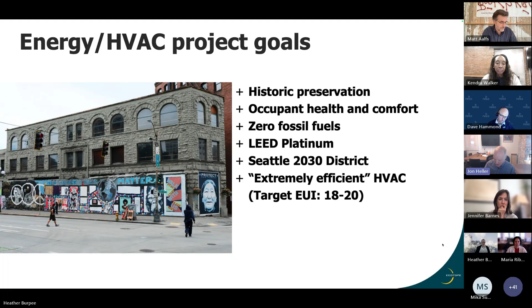Next slide. So the first focus on this shell of a building was bringing the heating load down as much as possible while maintaining the historic character of the masonry walls inside and out. In order to have a well-insulated envelope while still maintaining a lot of the exposed masonry, we focused on getting the best windows available—triple pane wood windows delivering a U value of less than 0.2. That allowed us to just insulate select areas of the wall, which were not as impactful to the indoor character.